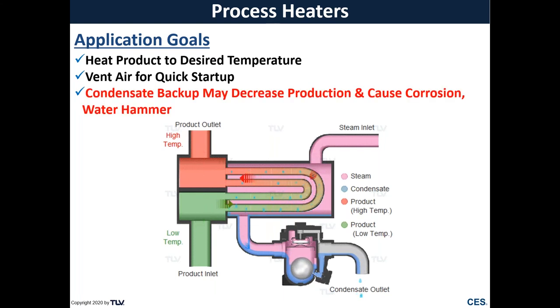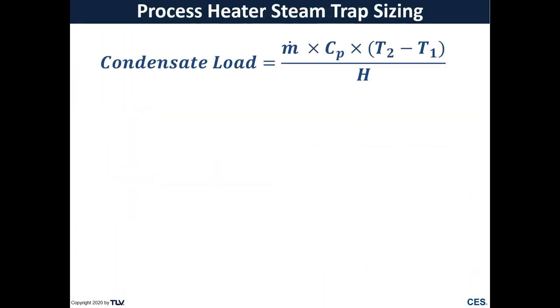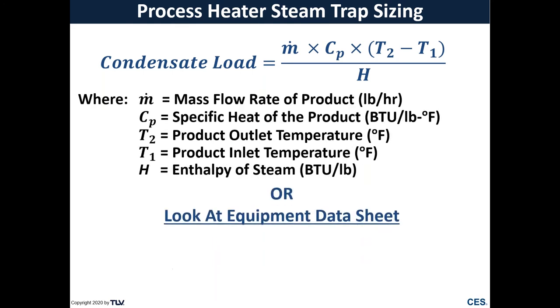And one very important consideration and goal here is to avoid condensate backup, because as we back up condensate, we could be decreasing production as well as causing corrosion and even leading to water hammer within that heat exchanger. Now, sizing a trap for a process heater, we can look at our heat transfer equation, MCP multiplied by our delta T. Or we could look at our heat exchanger data sheet, and that should give us the information we need for how much condensate is going to be produced out of this heat exchanger given our operating conditions.